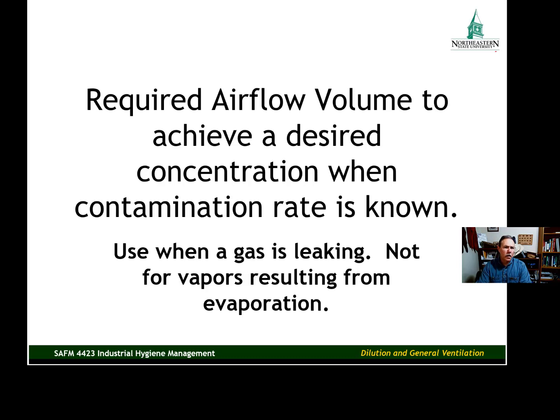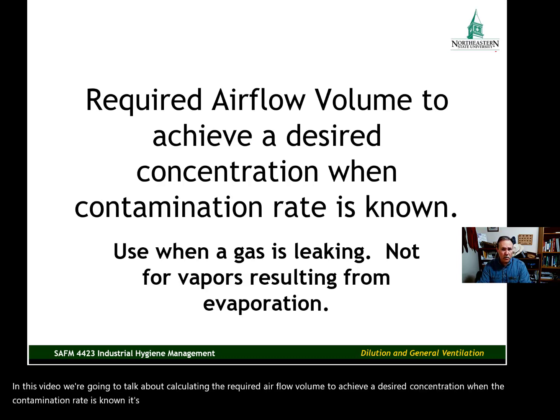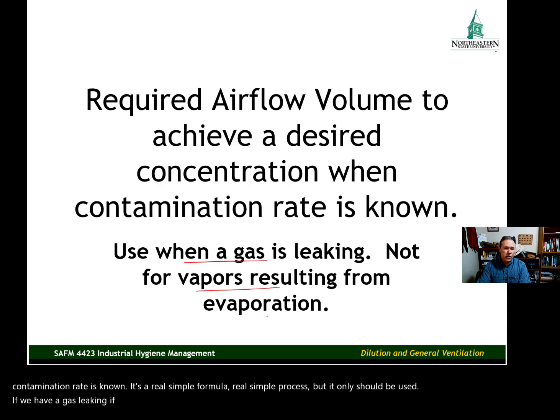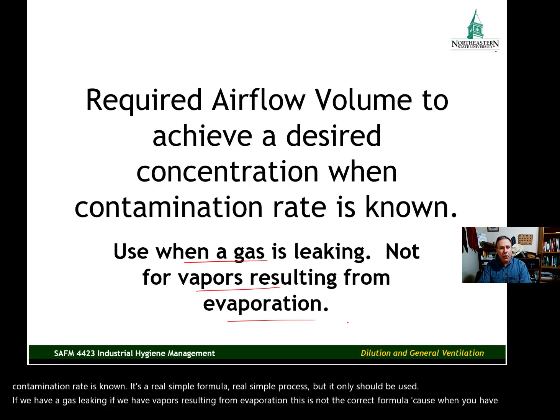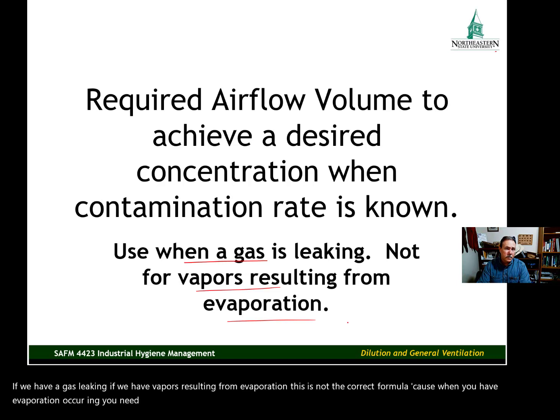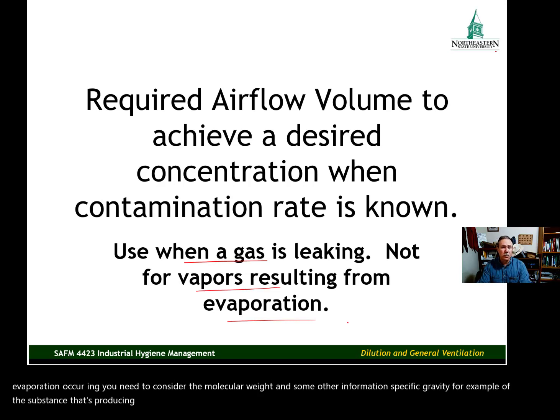In this video we're going to talk about calculating the required airflow volume to achieve a desired concentration when the contamination rate is known. It's a simple formula and process, but it should only be used if we have a gas leaking. If we have vapors resulting from evaporation, this is not the correct formula, because when you have evaporation occurring you need to consider the molecular weight, specific gravity, and other substance-specific information.